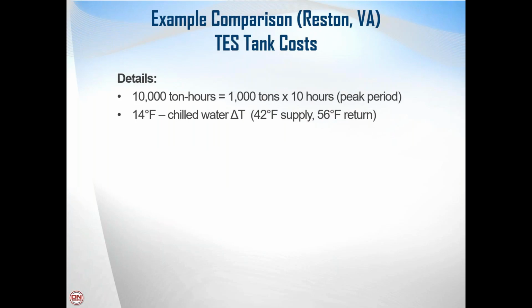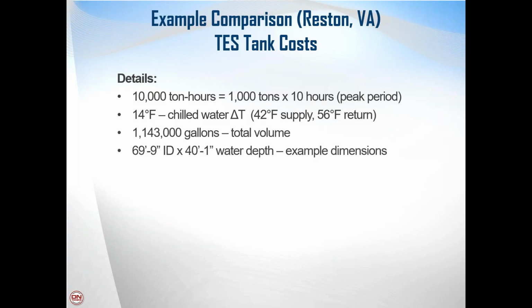So comparably, the thermal storage tank size for that system would be about a 10,000 ton hour requirement. And that's because they have 1,000 tons of cooling. That's what they need. And their peak period of time is a 10-hour peak period that they want to shift their electric load. So 1,000 tons, 10 hours, that's how we get the 10,000 ton hours. And their chilled water system had a delta T of 14 degrees Fahrenheit between their supply and return temperatures. For that size system, they would need about a 1.1 million gallon tank. And I'm showing you example dimensions of that tank, roughly 70 feet inside diameter by 40-foot water depth.